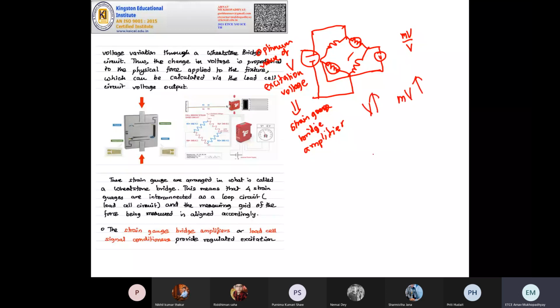But if you are designing some standard system, say using a microcontroller, you will require a normalized input. Normalized input means if nothing changes in your Wheatstone bridge, then the output voltage will also remain fixed, even if your excitation voltage is changing. How is that done? It is done using a new unit called mV per V, that is millivolt per volt. Your signal conditioner will output this value.